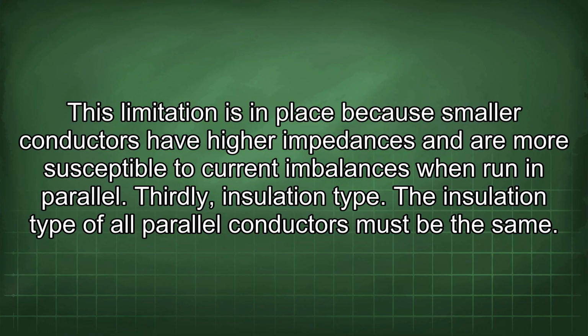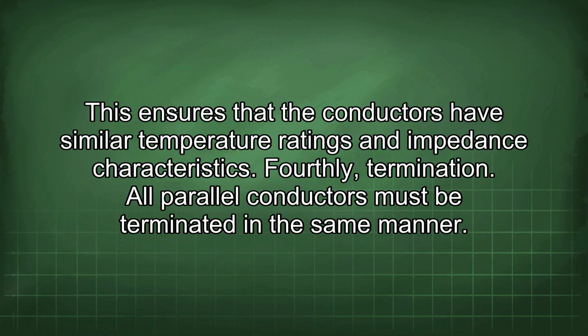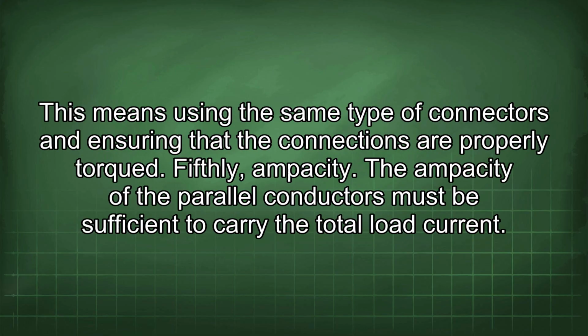Thirdly, insulation type. The insulation type of all parallel conductors must be the same. This ensures that the conductors have similar temperature ratings and impedance characteristics. Fourthly, termination. All parallel conductors must be terminated in the same manner. This means using the same type of connectors and ensuring that the connections are properly torqued.